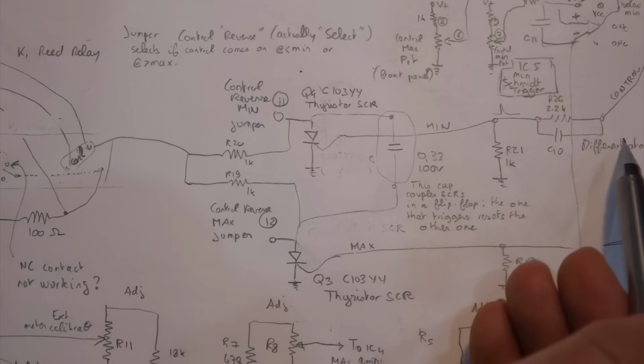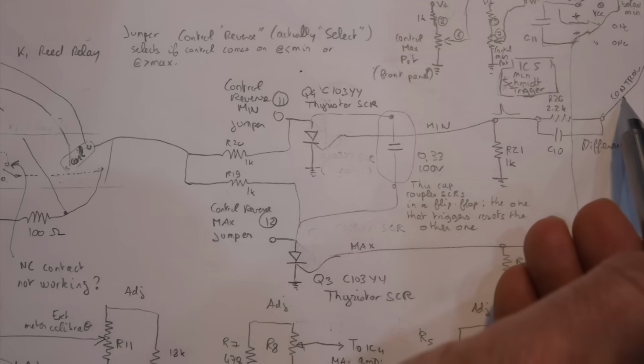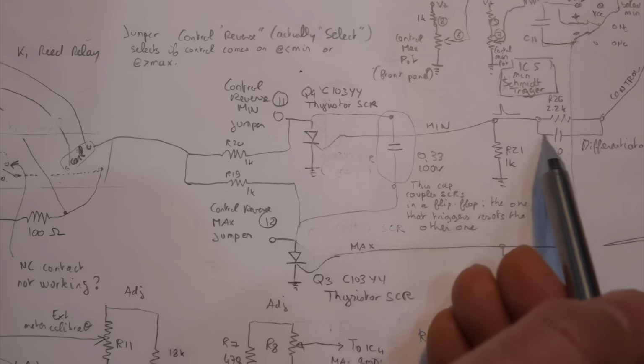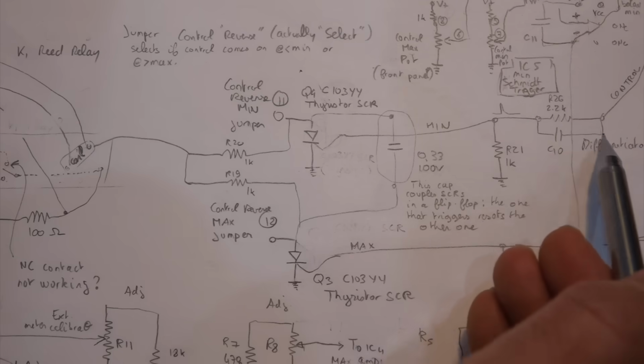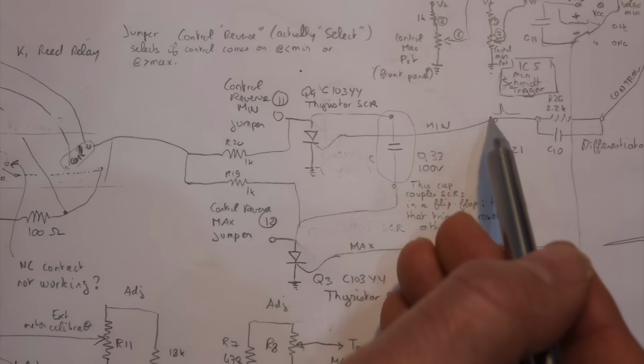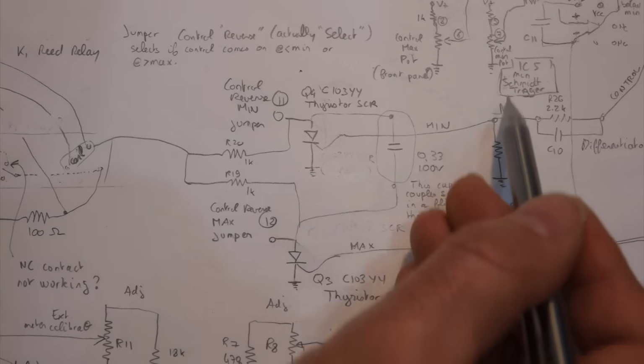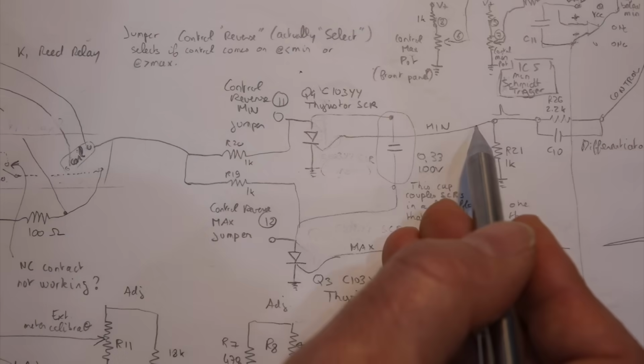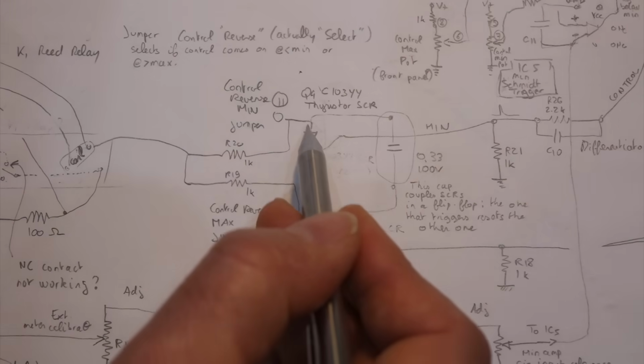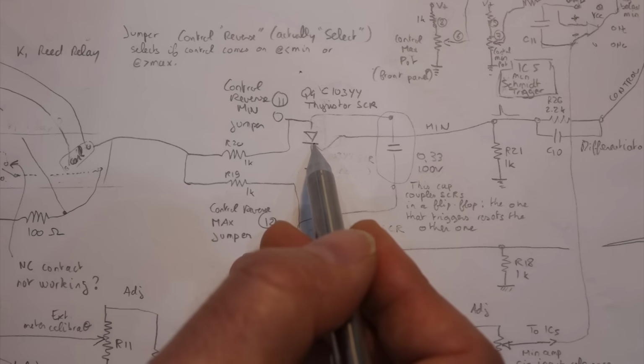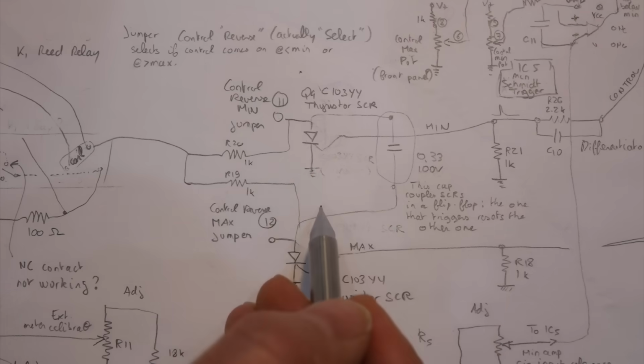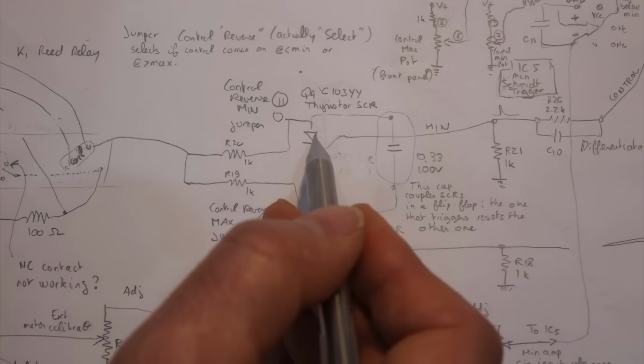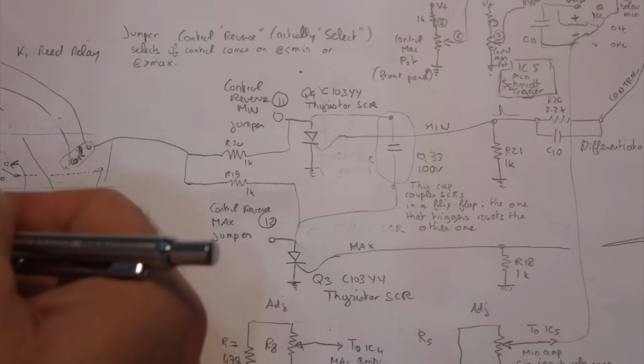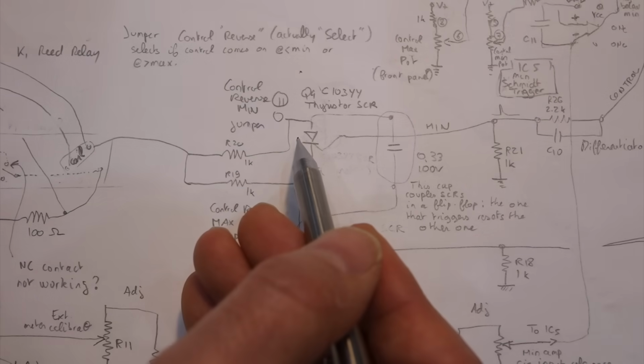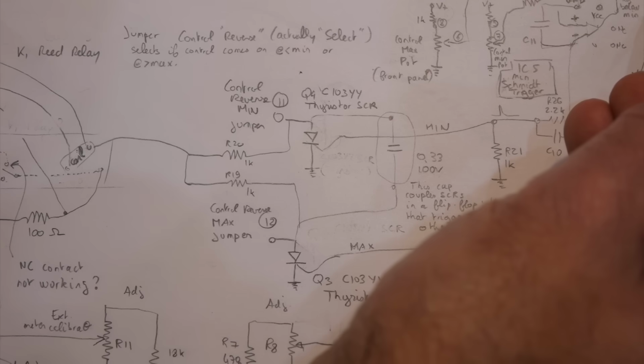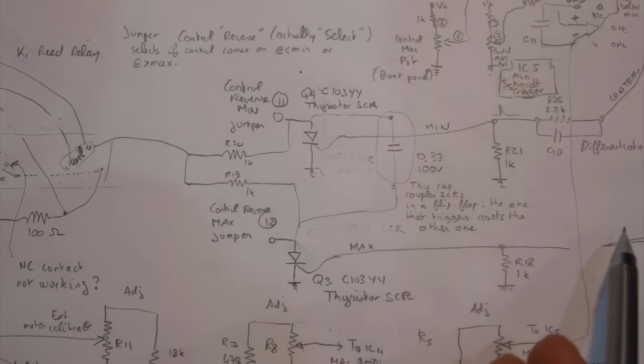But what happens is that the min level, when it comes up, is not directly coupled to it, it's differentiated, so it only gets a pulse. So when it goes through the minimum, it goes high, and that will trigger this guy. Thyristor or SCR, so once it's triggered, it stays on even if it goes back to zero. So this one is on and stays on, so your control starts past the minimum. And then this guy is the maximum.